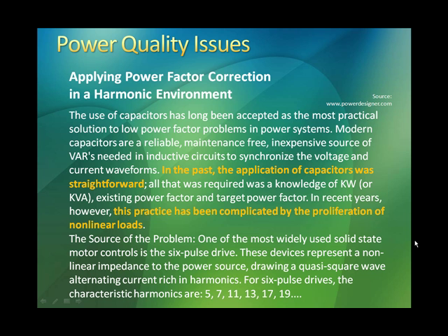Literally, electricians only needed to know what the kW or kVA was, and you could size what was needed. The problem today is we have a lot of solid-state controllers and switching power supplies. These devices represent nonlinear impedance, and consequently these capacitors can get into an overcurrent condition. It can set up a resonance between the capacitor and these drive circuits. So adding capacitors can actually create more of a problem than if you didn't. A capacitor is not a noise reduction device. It exacerbates the problem. One of the key benefits of the PowerWorx is combining surge and spike protection, noise reduction, along with capacitance. We're able to not only not increase the noise levels, but we will decrease them. We have specialized types of capacitors that are harmonic resistant, so we can solve the problem and still provide the benefits of power factor correction.